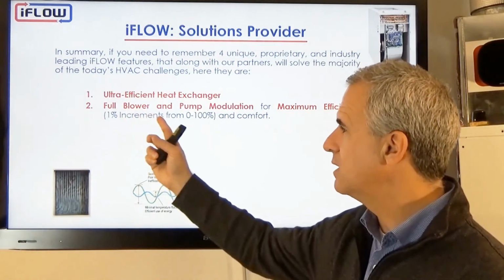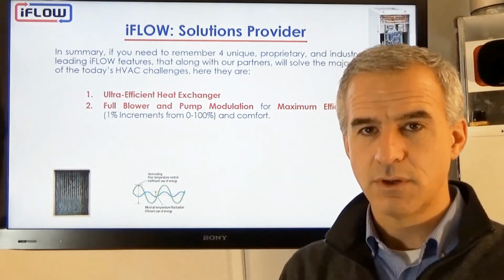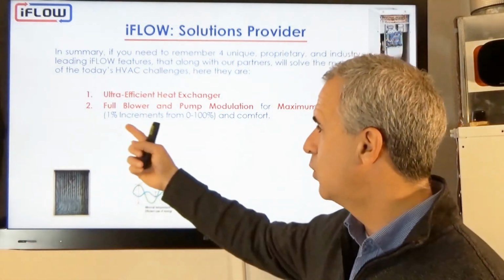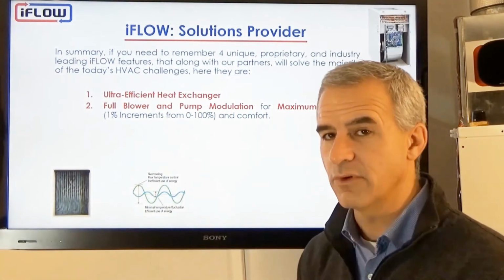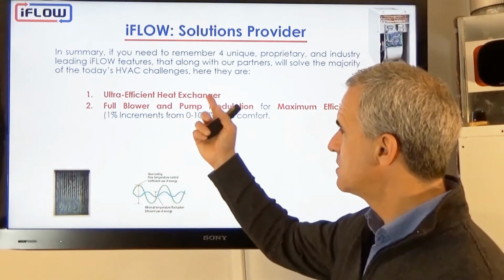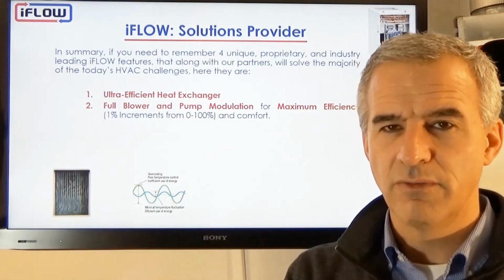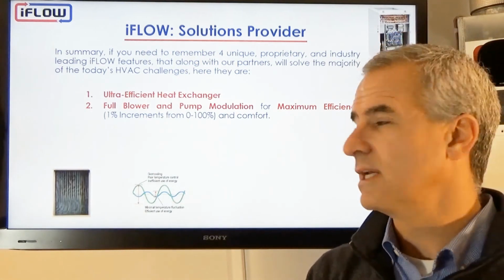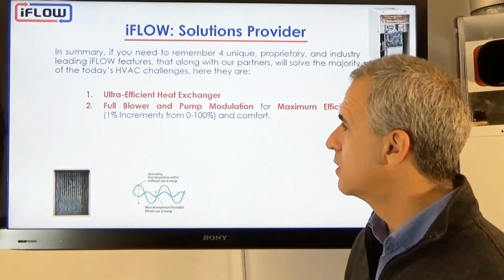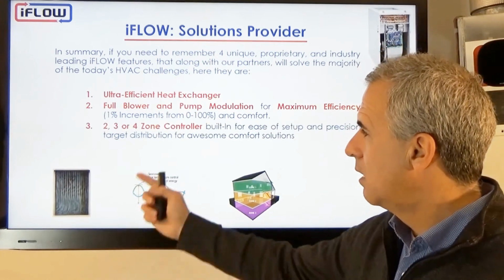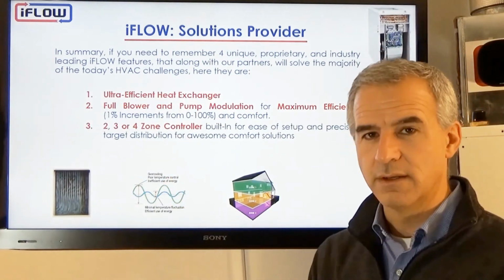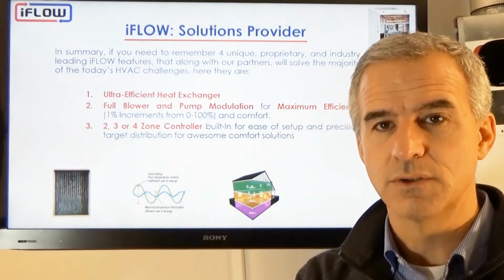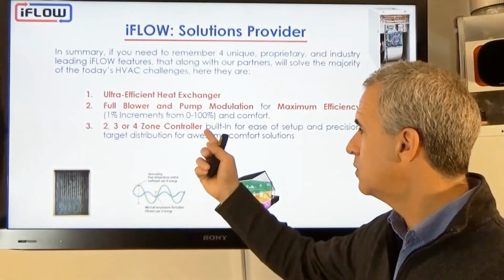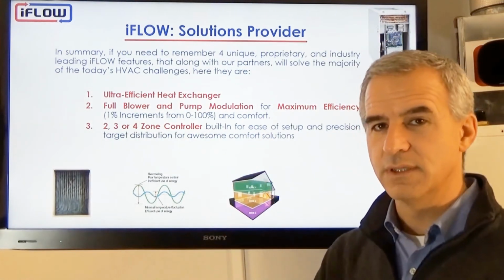We have full modulation of our blower and pump modulation to achieve maximum efficiency. So again, we can modulate that blower from 0 to 100% in 1% increments, and that's great comfort. On the pump modulation side, we can't go right to 0. We go from about 35% up to 100% on those PSC motors. We have zone control. So again, we can do single zone, but we can also do 2, 3, or 4 zone control. All of that is built in.